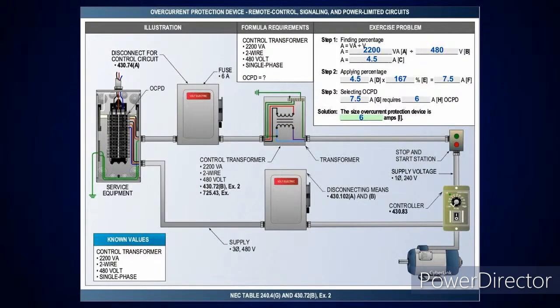Now, looking at this one, I've got a transformer here. What we want to do is go over and look at table 450.3(B). If I have a current that's more than 2 amps but less than 9 amps, it tells you on that transformer to take it at what? 167%. Now, if the current was 9 amps or more, you take it at 125%. And if it was less than 2 amperes, you take it at 300%. But here, we're going to figure out what the amperage is for that transformer.